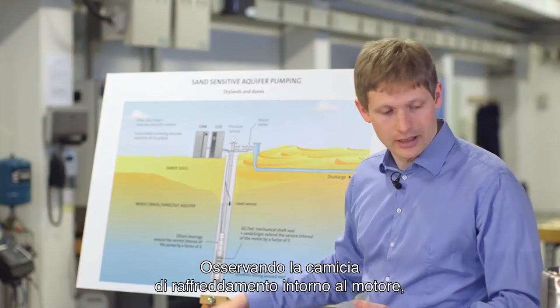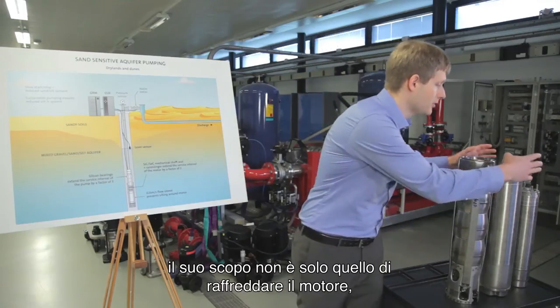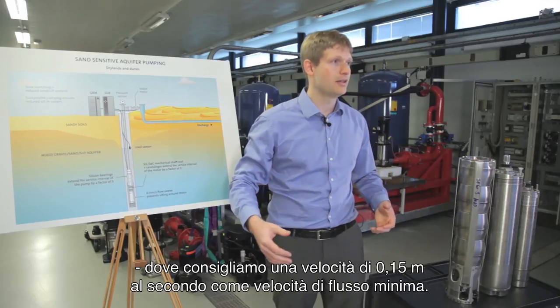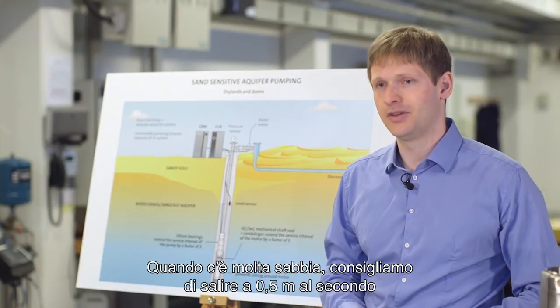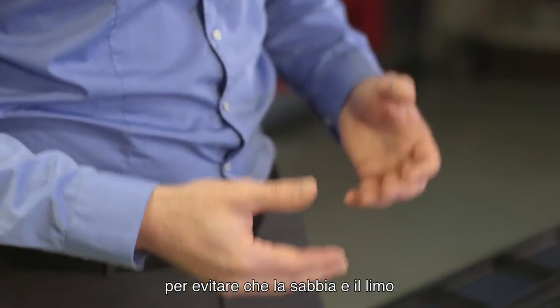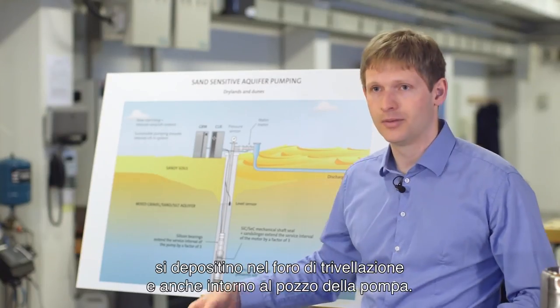When we look at the cooling sleeve which is around the motor, the purpose here is not only for cooling the motor — where we recommend 0.15 meters per second as a minimum flow velocity. When we have a lot of sand, we would recommend setting this limit to 0.5 meters per second in order to avoid sand and silt settling down in the borehole and around the pump.